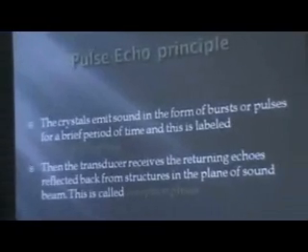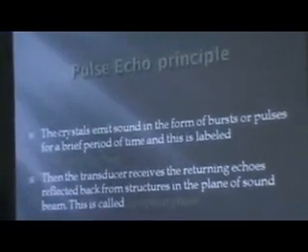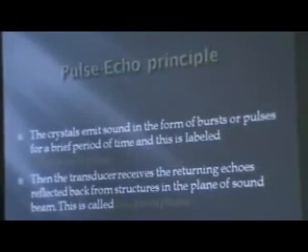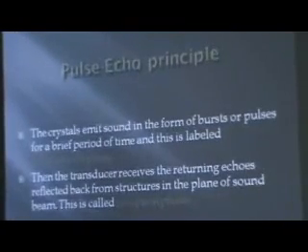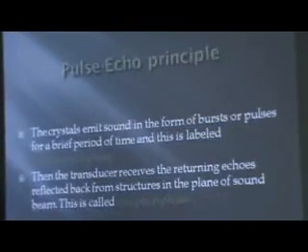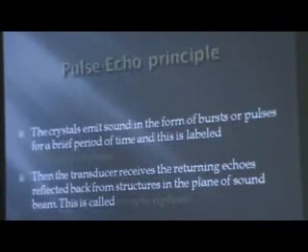Now the crystals produce the ultrasound waves not continuously, but in bursts or pulses. The electrical current strikes, the crystals vibrate, and then they produce the ultrasound wave in a pulse or burst. Then for some time the ultrasound generation stops. Then the crystals start receiving the ultrasound waves which are reflected back from the various tissues of the body.